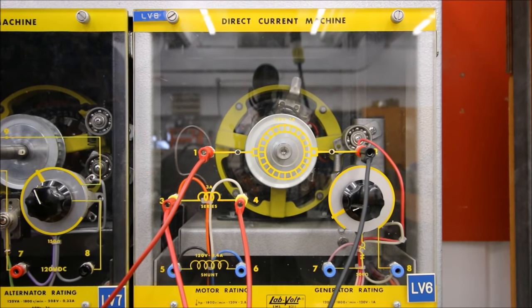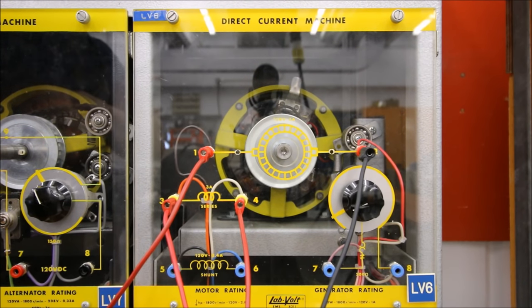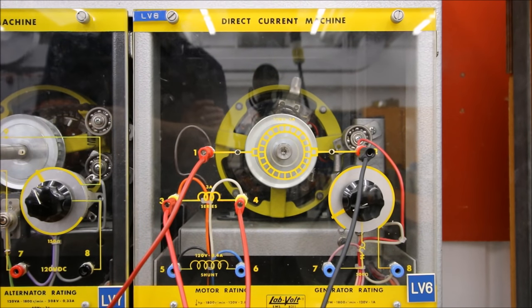Oh! You can see that the motor is going faster and faster and faster. It's making me nervous there, so I had to shut off the power. This thing just goes faster and faster and faster. There's nothing to regulate the speed of a series DC motor without a load.